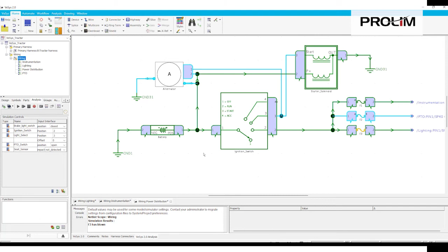Okay, there we go. So there we can see that F3 is yellow. If we hover over this yellow, we can see it looks like the fuse rating is a 10 amp, and I know from experience that this should have been a 30 amp fuse. We can even see down here at the bottom the suggested rating for this is 35 amp. So let's go ahead and double click this guy. And again, based on previous understanding, I know this should have been a 30 amp fuse. So it looks like maybe the designer has just assigned the wrong part number.